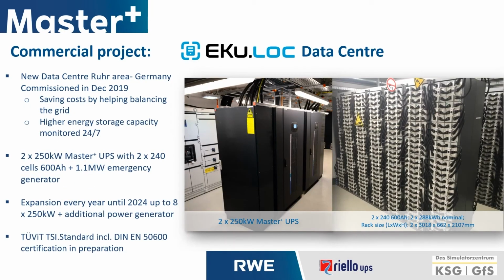In addition to the pilot projects, there are also fully operational commercial installations. In the images on the right hand side, you can see the system that is installed at a data center in Germany, which was commissioned in December 2019. Since installation, this system has been helping to save costs by balancing the grid and hence benefiting from those markets, in addition to providing higher levels of energy storage capacity and additional resilience in terms of a system that is fully monitored 24/7. The system comprises two 250 kilowatt UPS systems with an additional 1.1 megawatts worth of emergency generation. This system will continue to be expanded year on year up until 2024, at which point they will have eight 250 kilowatt UPSs plus additional power generation on site.